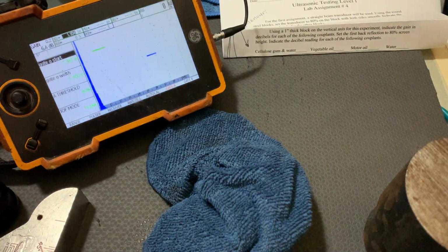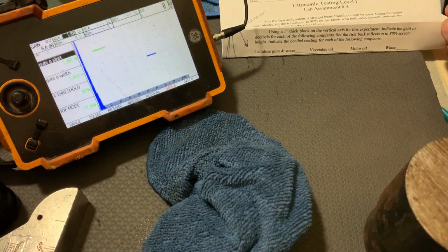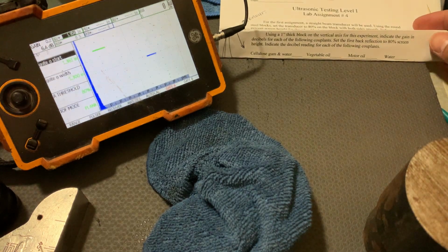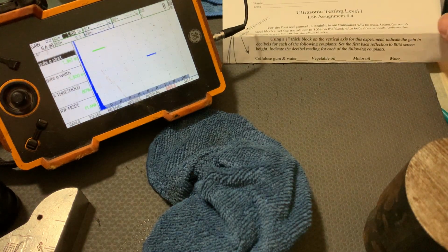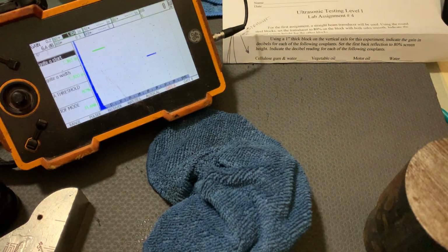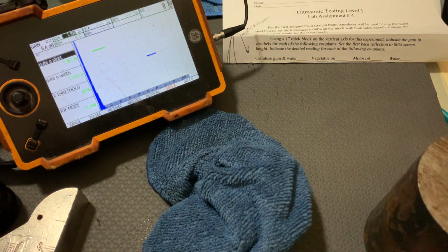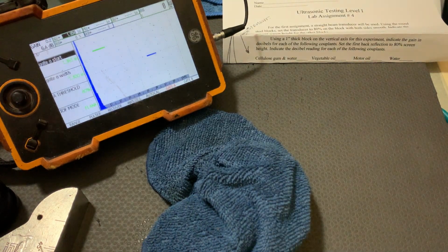So this one here, we're using a 1-inch block on a vertical axis for this experiment. Indicate the gain in decibels for each of the following couplants. Set the first back reflection to 80% screen height. Indicate decibel readings at each of the following couplants. So we're going to be switching our couplants.